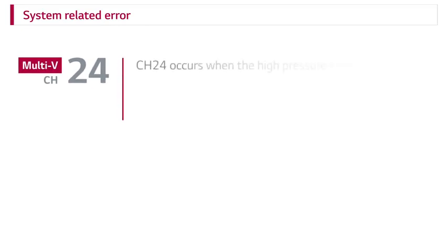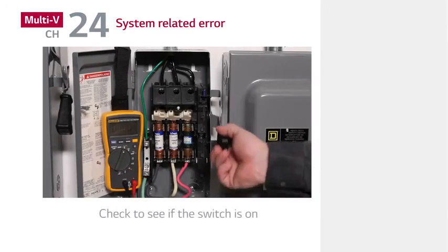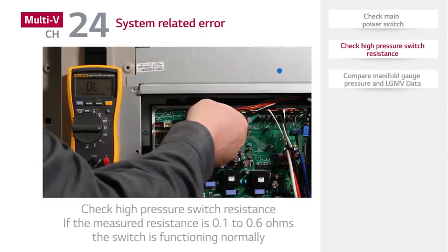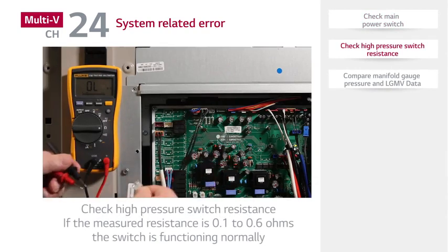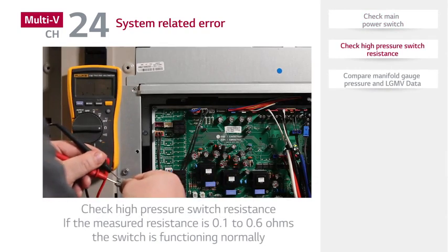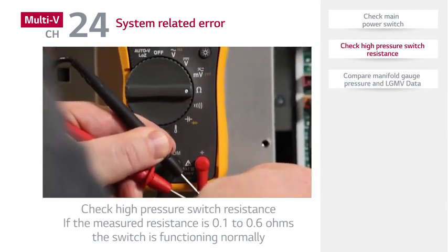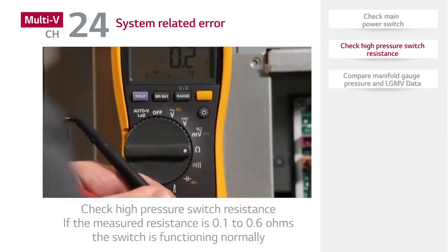A CH-24 error indicates the high-pressure switch is opened. First, check the power. Next, check the high-pressure switch resistance. If the measured resistance is 0.1 to 0.6 ohms, the switch is functioning normally.